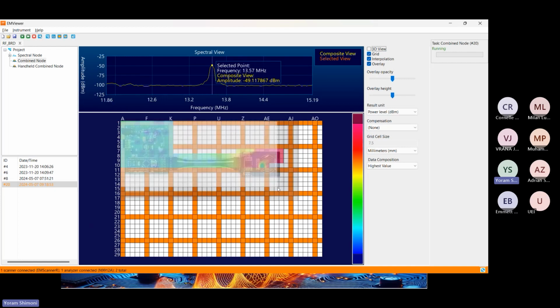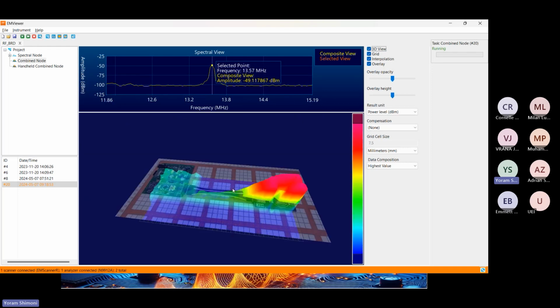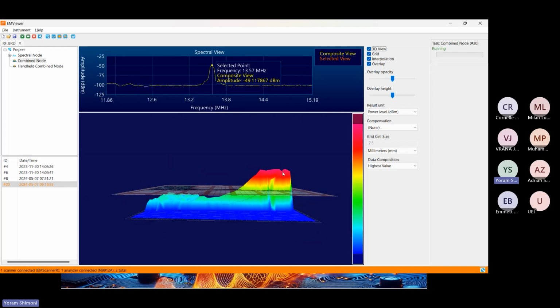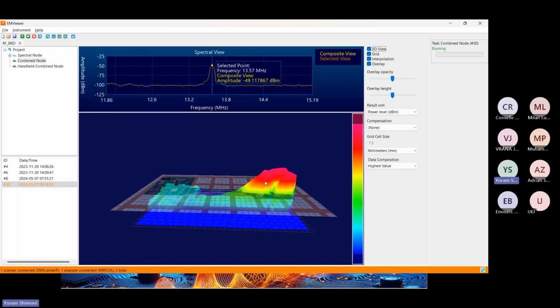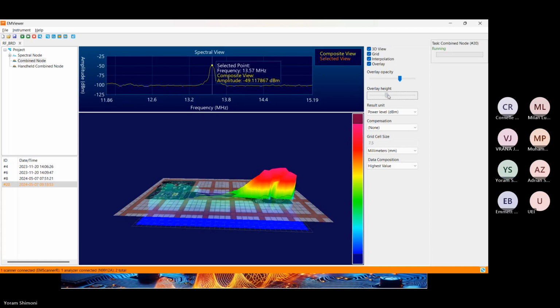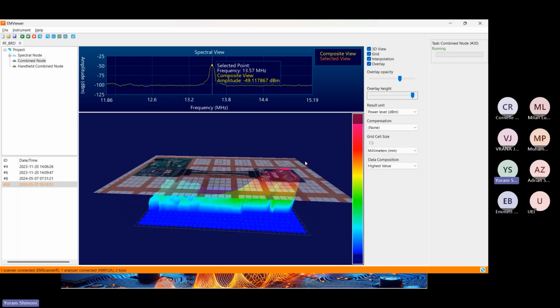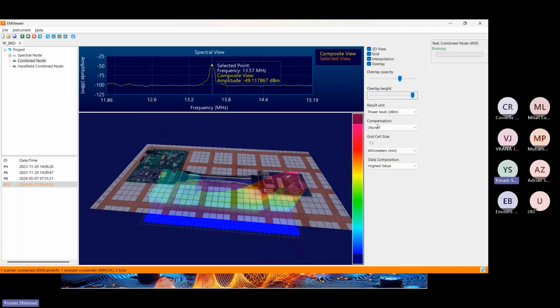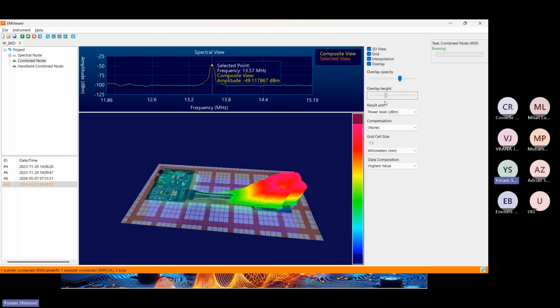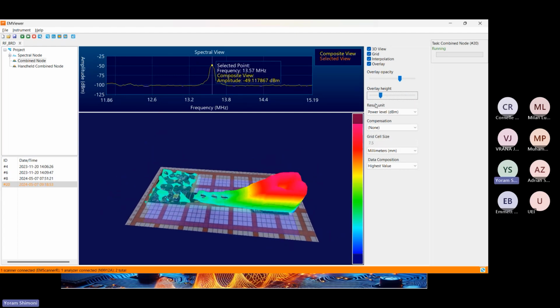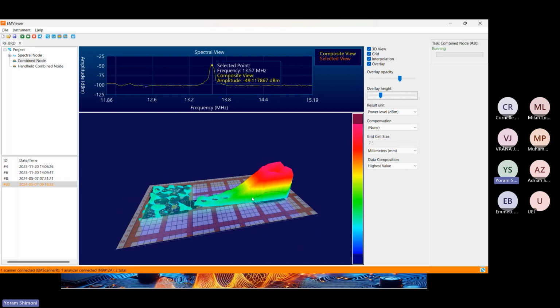Here you can actually see that very clearly. So the 13 megahertz signal is being generated by that processor here, on this board — you can see the IC here. But the problem is that it's being distributed through the cable to the main board, and that's essentially what caused the failure.